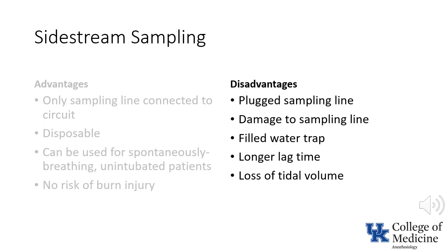There are disadvantages to sidestream sampling. The sampling line has a small diameter and may become plugged with secretions. Furthermore, it may become damaged, resulting in erroneous values. In addition, the water trap may become filled with condensation, resulting in inaccurate readings. The slower response time due to the need to move sampled gas through the length of the sampling line to the measurement site is inconvenient when awaiting results to confirm correct placement of a tracheal tube. Finally, there is the loss of tidal volume discussed previously.